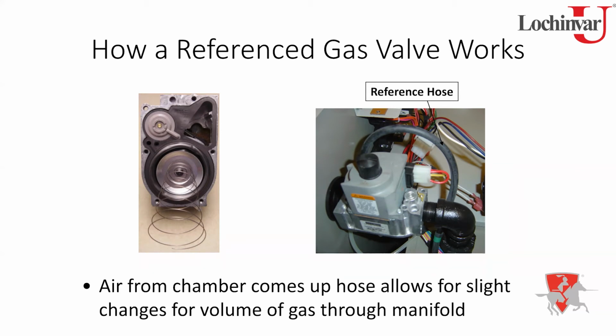So it's referencing some other area. What we're doing is basically adjusting the spring in the regulator like you would any other regulator. You're turning that spring in, pressing down on a diaphragm, which opens it up to allow gas to flow. So we're going to preset that at a certain pressure. Then, based on the pressure in this reference hose, which goes down and connects to the front chamber, it's looking at the pressure that the fan is blowing down into. It's taking that pressure and pressing that regulator down even more.